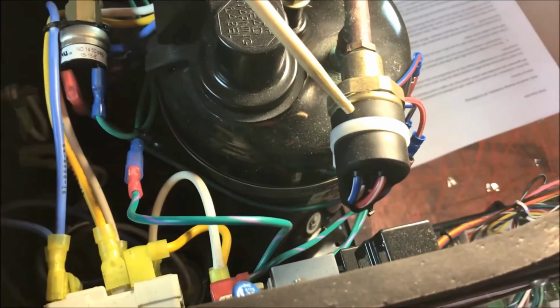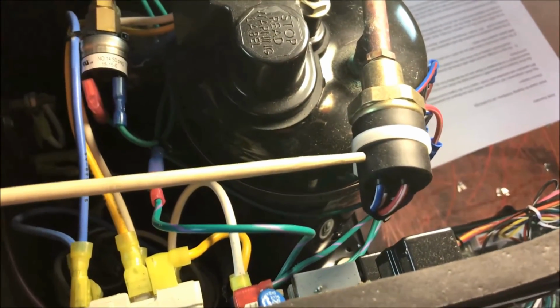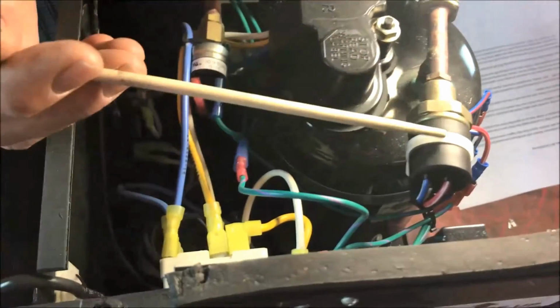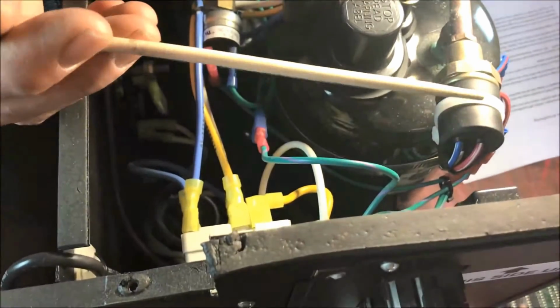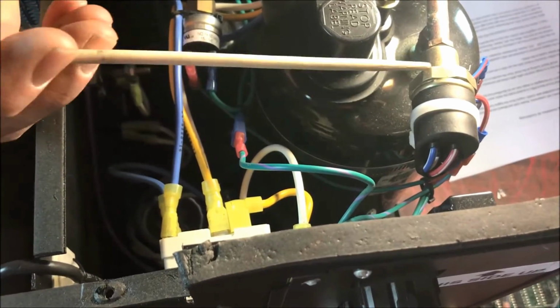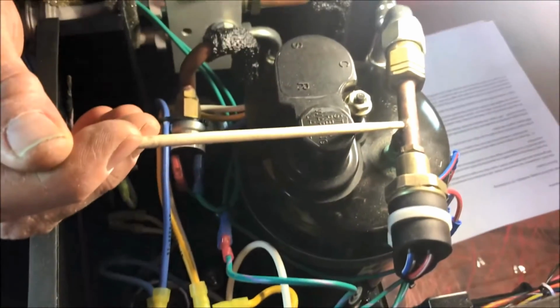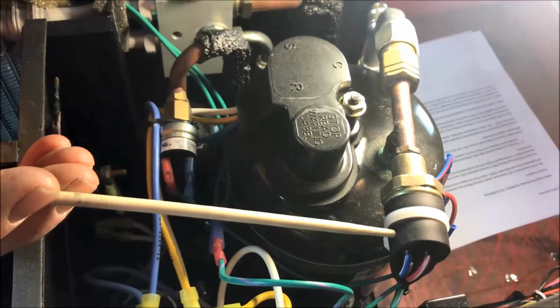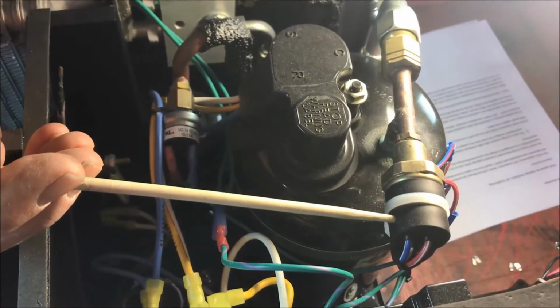So, the Trinary Switch monitors the pressure of the high side. It cuts out the compressor at 350 PSI and below 40 PSI on the high side. It also controls the condenser fan. When the discharge pressure reaches 225, the trinary switch closes. When the pressure reduces down to 175, the trinary switch will open and the condenser fan will stop.